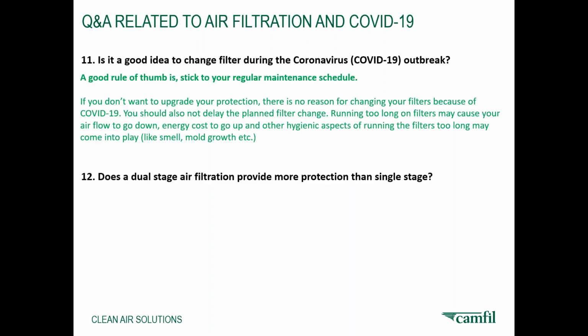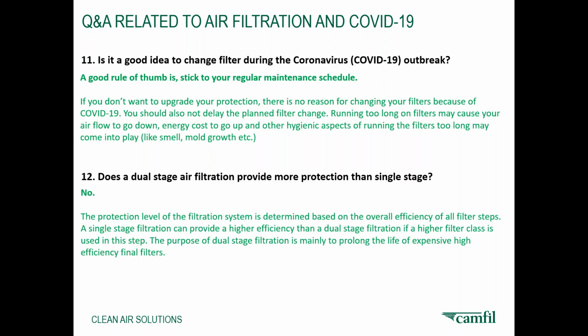So the last question we found at Camfil is, does dual stage air filtration provide more protection than single stage? Definitely, providing if you put 2, 3, or 4 filters, it will clean the air more. But that doesn't mean dual stage protection is always higher. The protection level is determined by the overall efficiency of the filtration system. If you place a pre-filter, a fine filter, and then a HEPA filter, the overall efficiency matters. A single stage product can actually provide higher efficiency. If you put a higher efficiency filter in the first stage, it will capture more, but the filter life would be less, because it is capturing a higher amount of particles, so the life of the filter would be shorter.